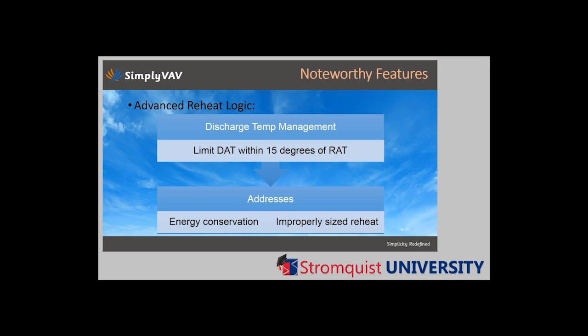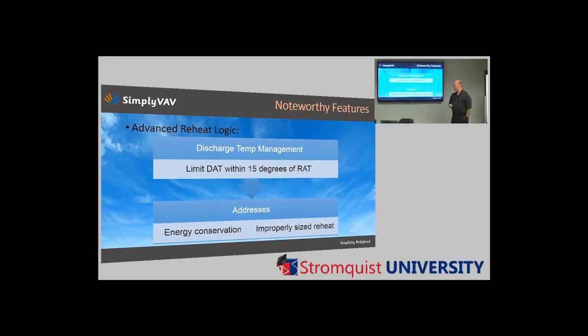Advanced reheat logic that says we're going to maintain our discharge air temperature within 15 degrees of our return air temperature, and obviously the purpose of doing this is to make sure that we operate the system not only simply but efficiently as well, so we're not wasting energy in our retrofit application.